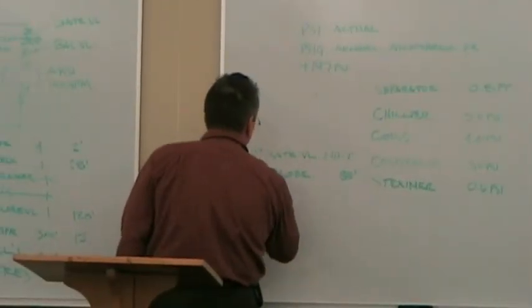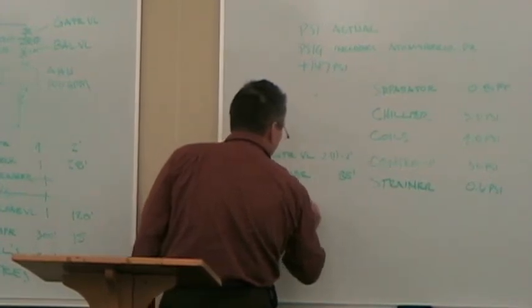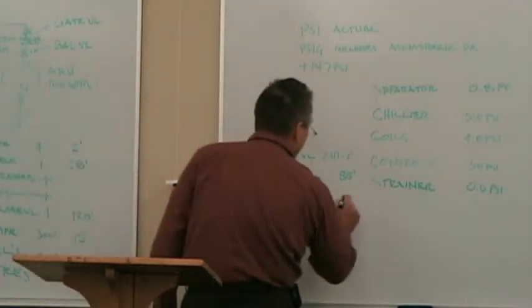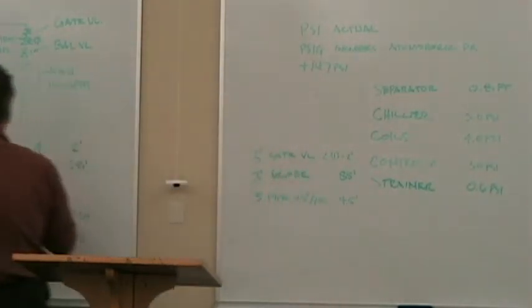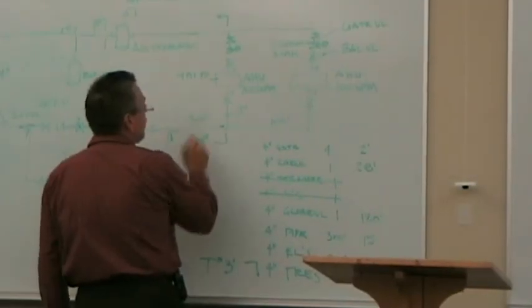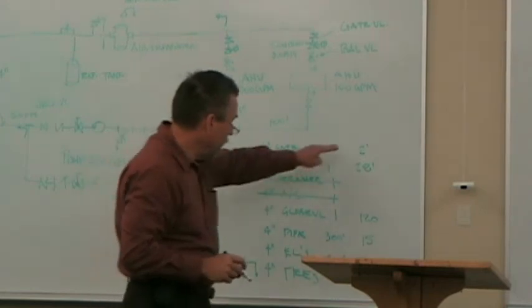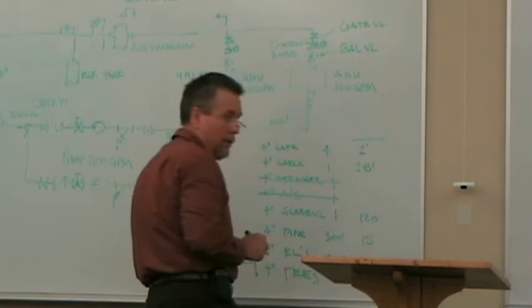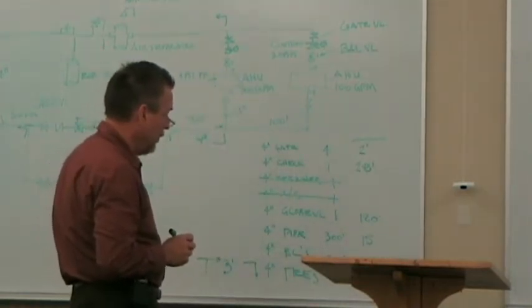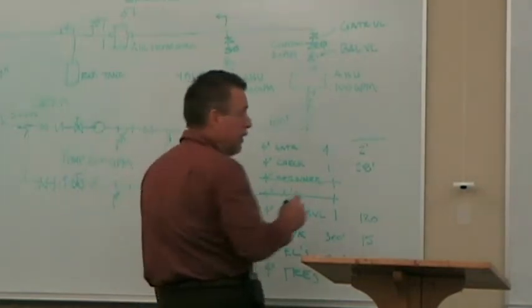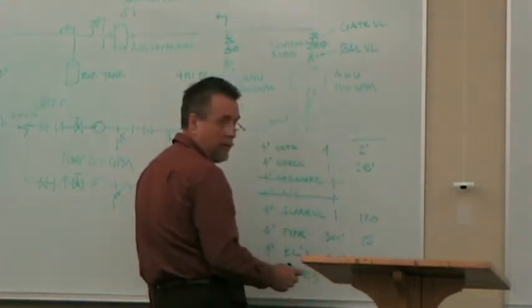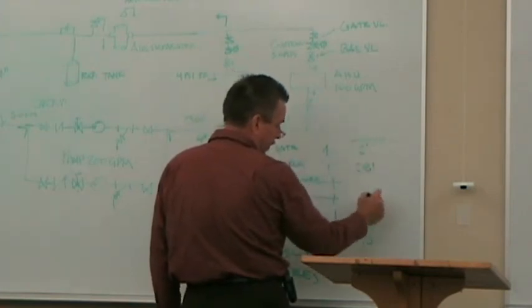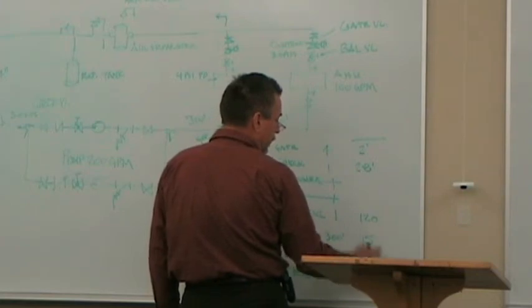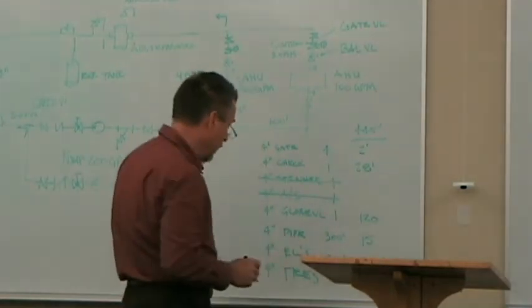And a 3-inch pipe, 100 gallons a minute, is 4.5 feet per 100. And let's just say we've got 100 feet of pipe, so that's 4.5 feet. Say if this is 100 feet, this was 300 feet. Okay, so now I've got all this added up. So what's this add up to, John? I added up everything. These numbers right here? Just those numbers? Yeah, 405. Pretty close. Or maybe it's 440. 445. 445 feet. Okay, so I've got a total of 445 feet.